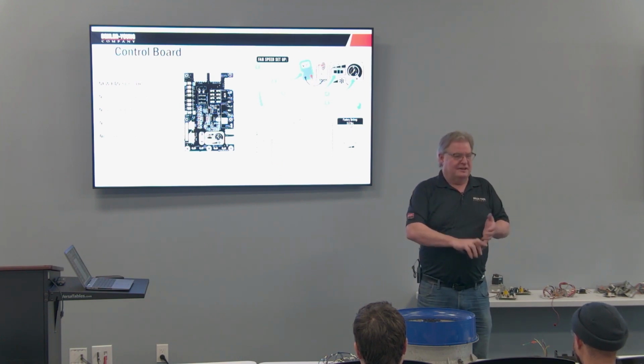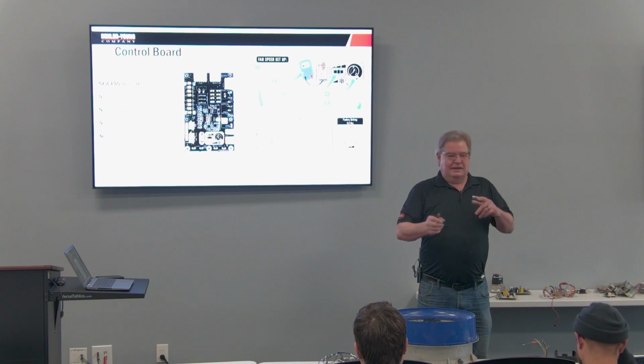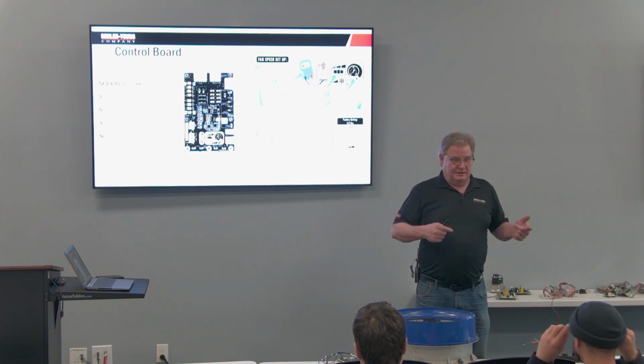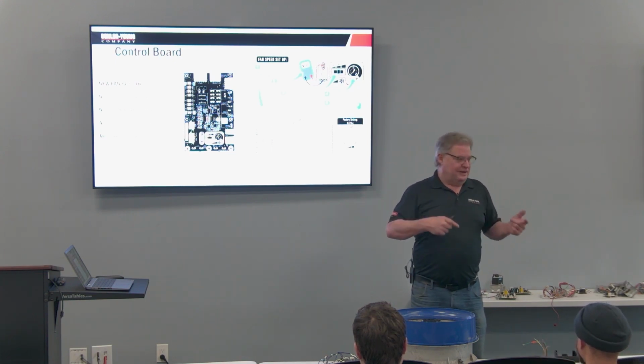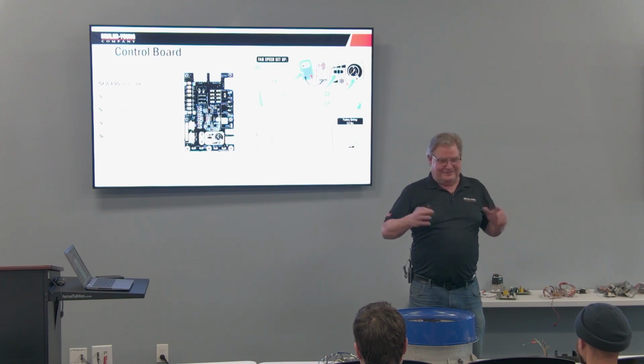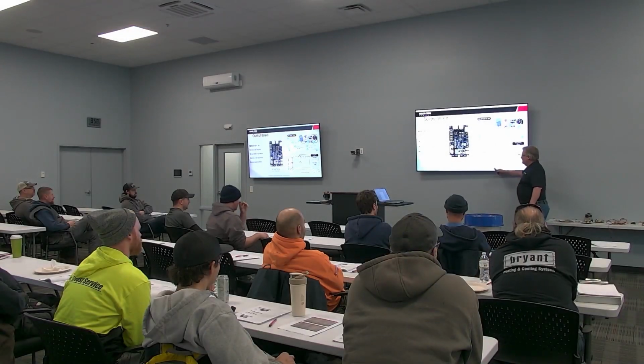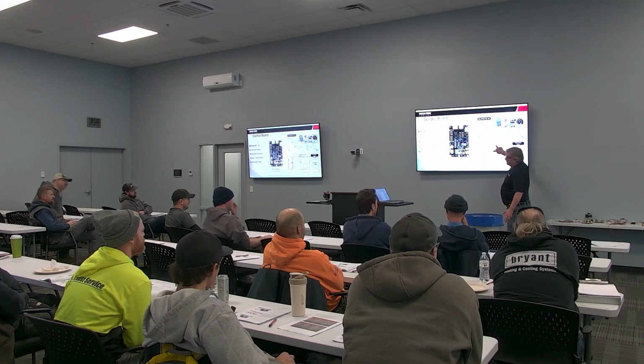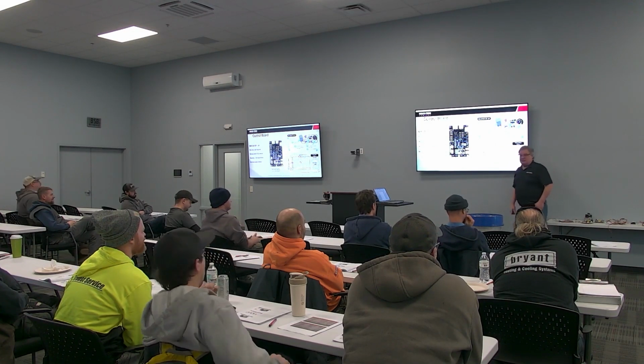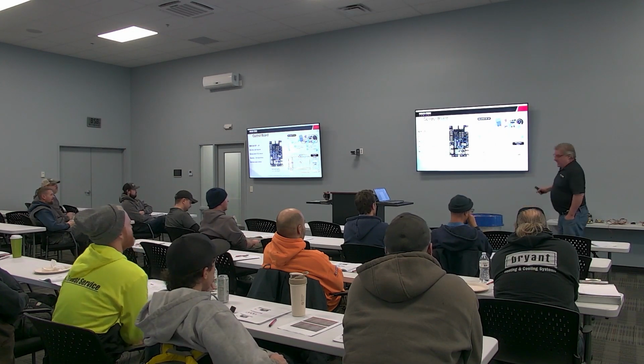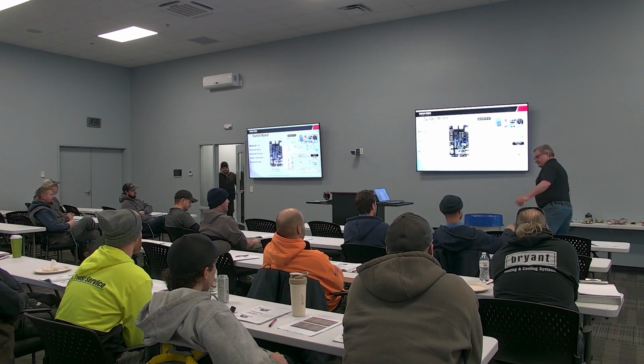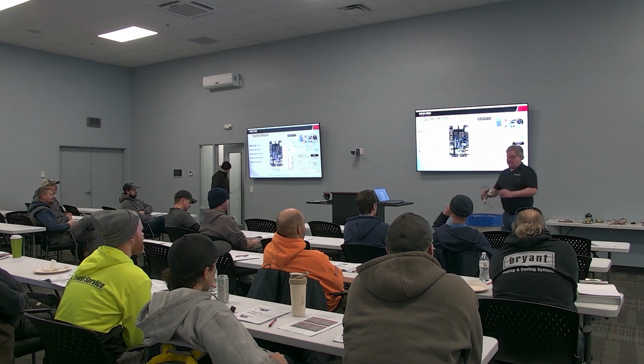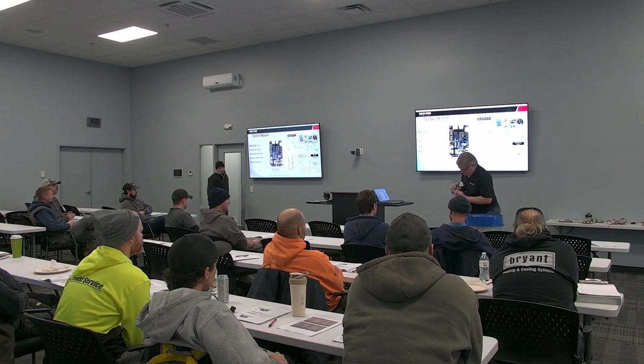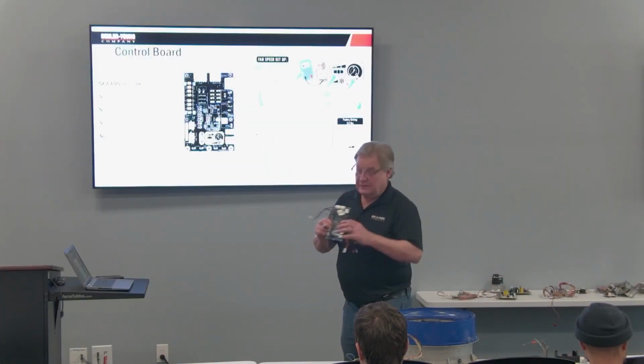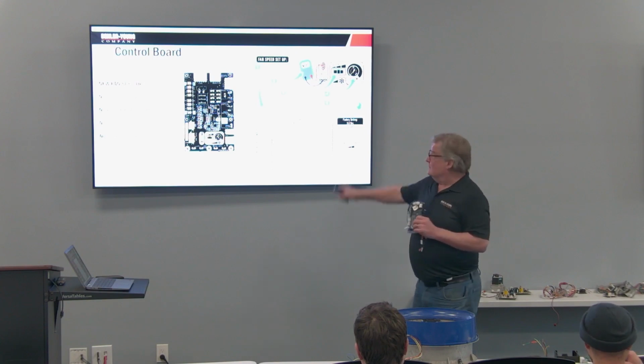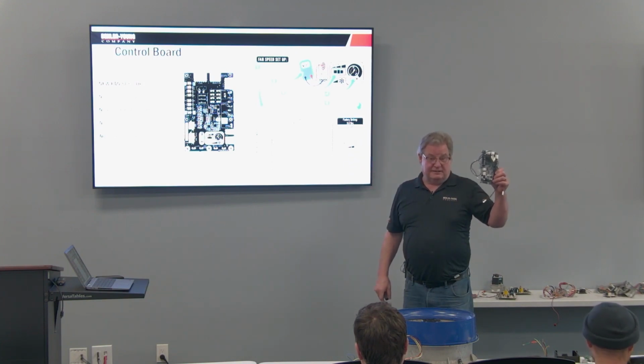But for instance, a 582 KE04 would be a 3-ton. An 05 would be a 4-ton. An 06 would be a 5-ton. An 08 is a 7.5. Okay. So we can figure out a CFM. Our static, we're going to talk about how to get that. It gives me a number, 9.7. That is where I'm going to set the dial on this. On the board here, I'm going to set this dial to 9.7 volts DC.